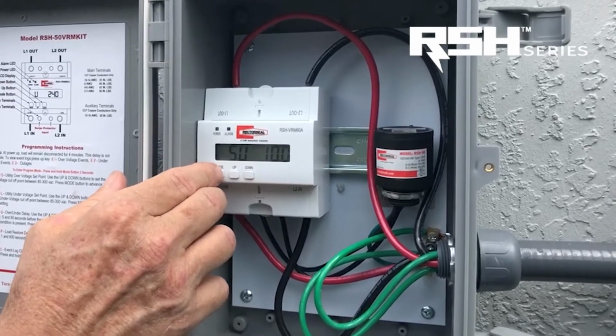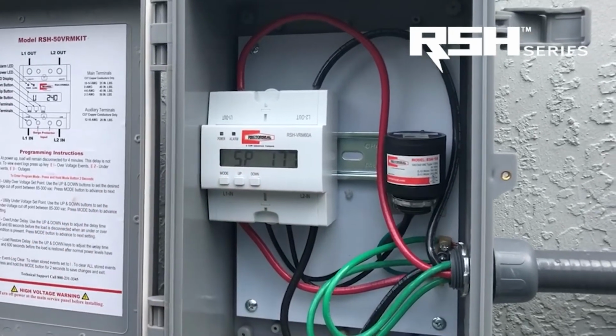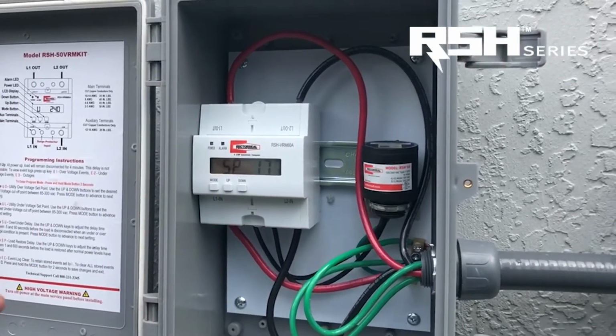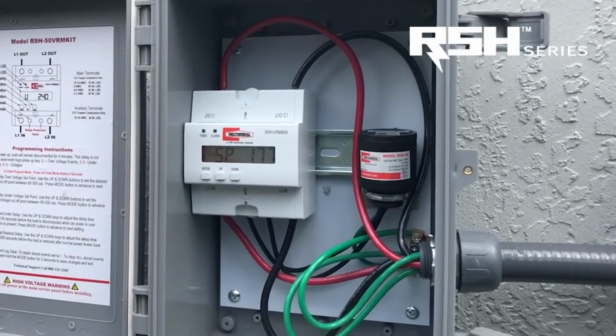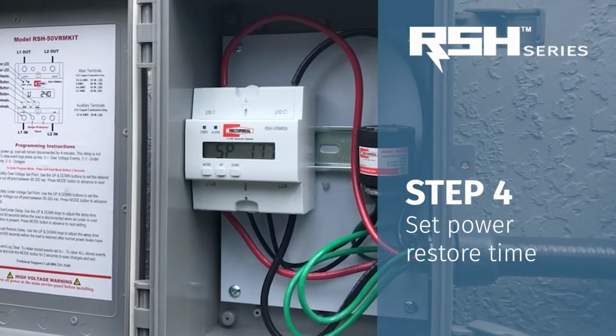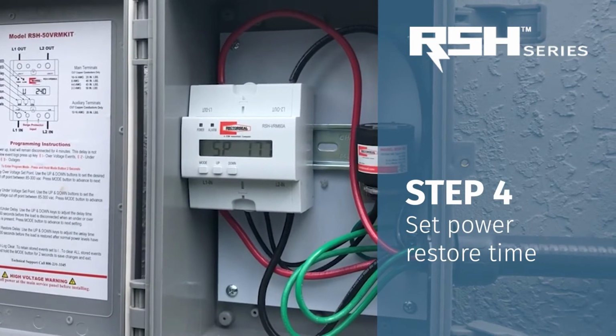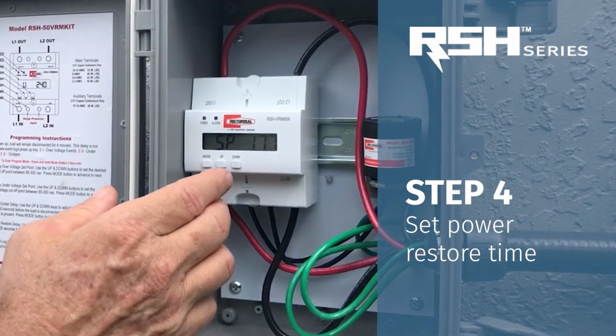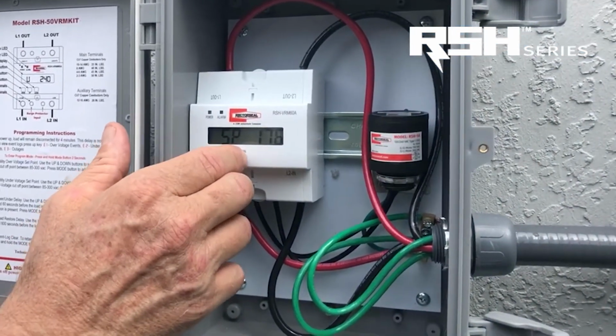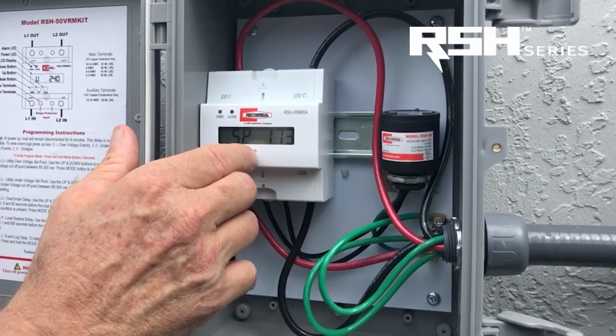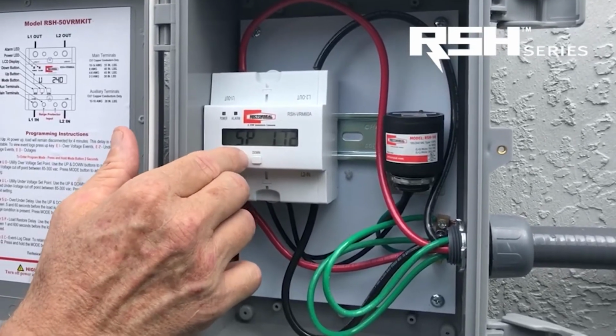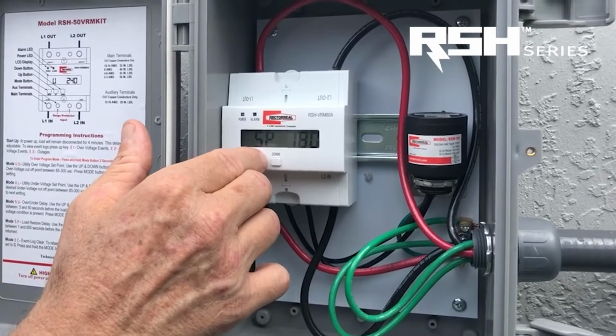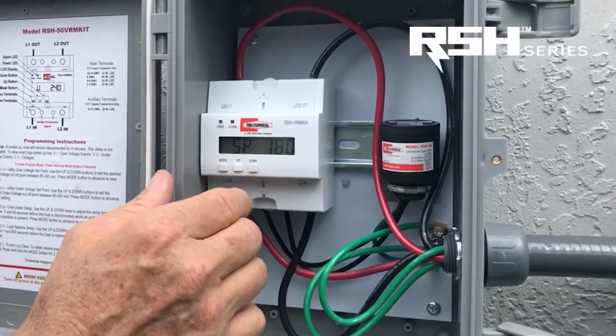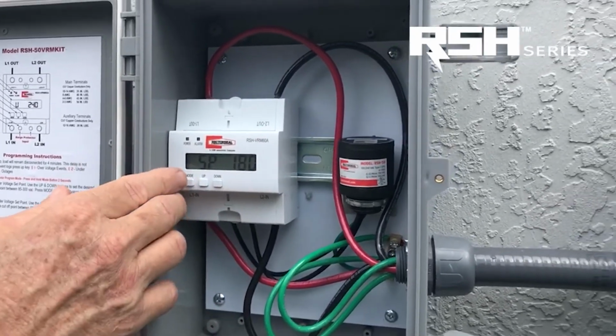So that's set. And then the next one is when you turn power back on. You can set a delay before power is restored to the condenser, and that is 0 to 600 seconds. So I'm going to set this up to 180 seconds, which is about 3 minutes, so we won't run into a short cycle situation. So now you're all set with the programming part of it.